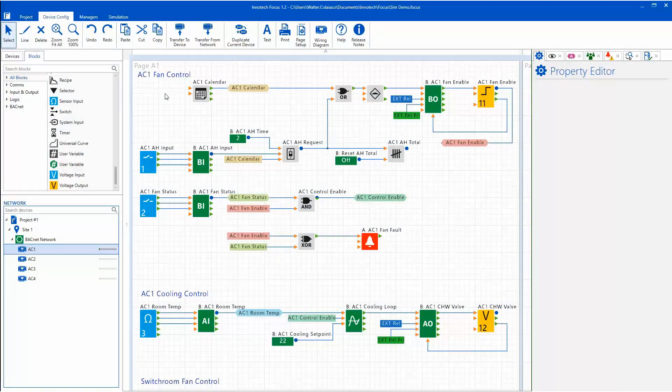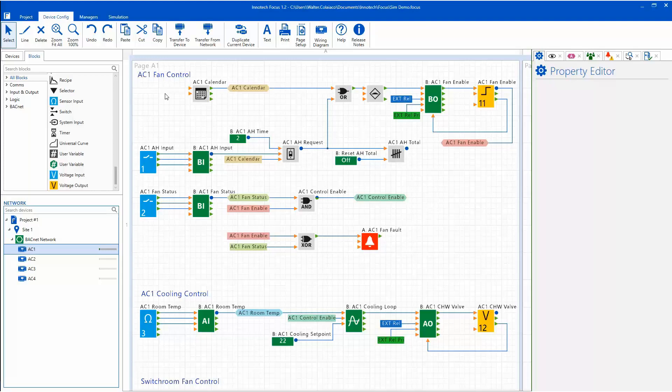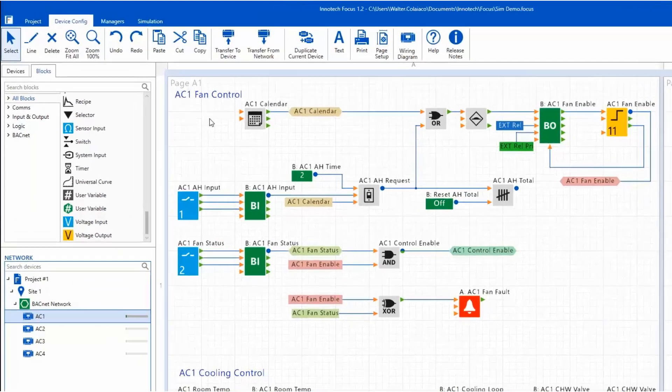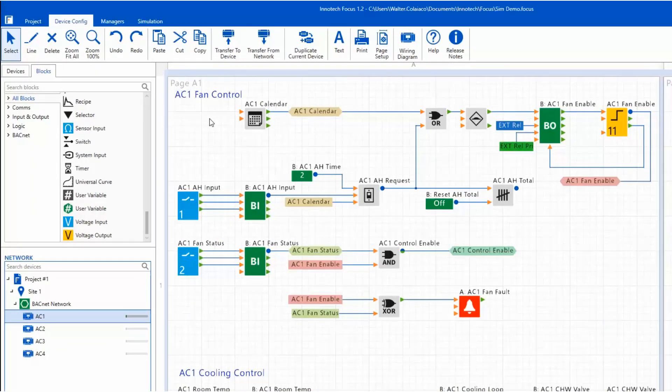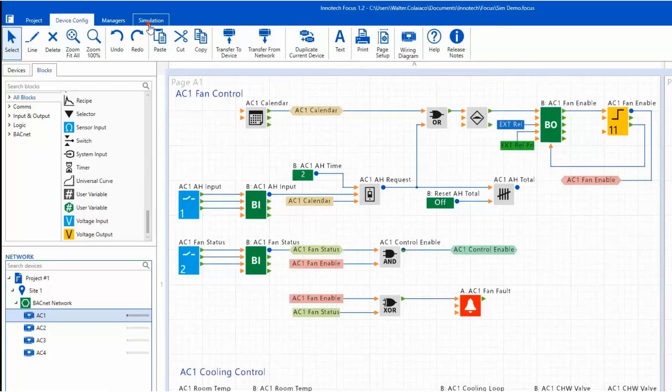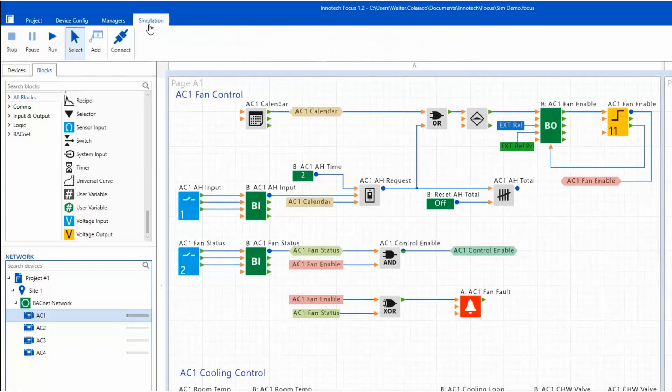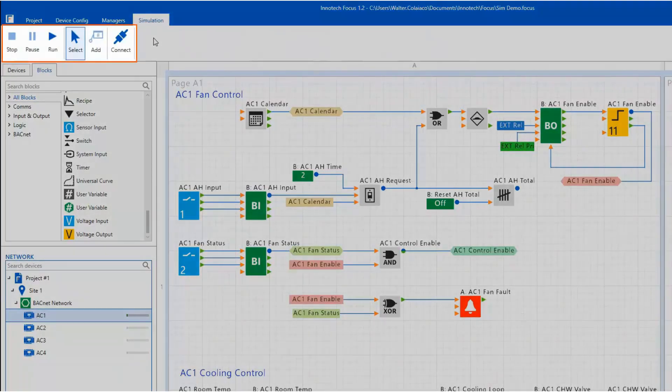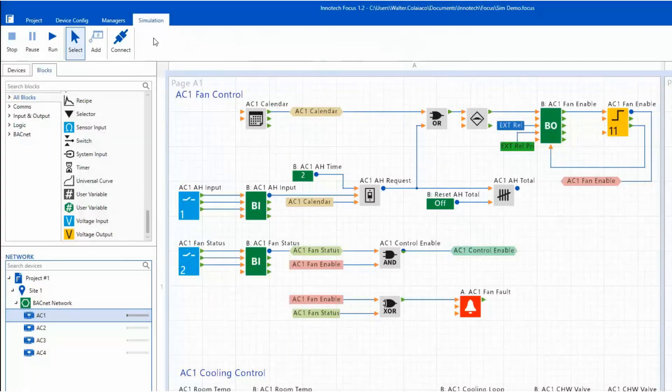During your configuration workflow, you have the option to simulate and test the controller logic directly within the Focus Programming software. This feature can be used to your advantage to test and alter logic tasks prior to site implementation and commissioning, which can save valuable engineering time. To access the simulator mode, ensure the device is selected in the network list, then click the simulation menu on the main toolbar. The ribbon changes to display the simulation options. To begin the simulation, click the Run button.